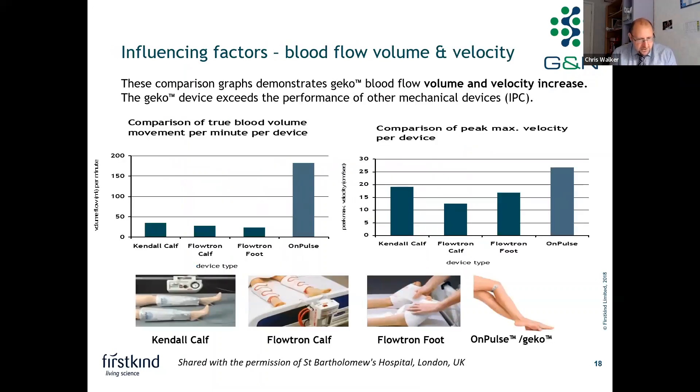How does geko compare versus IPC? A study conducted at St. Bartholomew's Hospital in London tested different IPC devices alongside Gecko, measuring the amount of blood moved per minute in millilitres per minute and the velocity of blood flow. Gecko moves a significant amount of blood compared to IPC devices, likely because it contracts the calf muscle more frequently. Interestingly, blood is moved at the same or similar velocity as IPC, which is deemed to be safe.